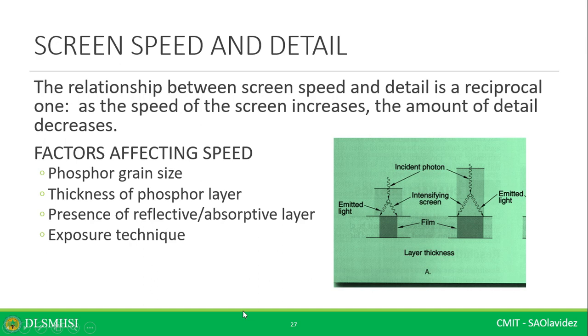Screens are also dependent on the technical factor used, particularly the KVP. IS, especially the rare earth intensifying screen, exhibits its highest response only when exposed to KVP between 80 to 85. The IS will exhibit a lower speed when exposed to either lower or higher factor than is recommended. However, in doing radiographic examinations, it is the thickness of the part under study that will determine the KVP that we use for every particular examination.